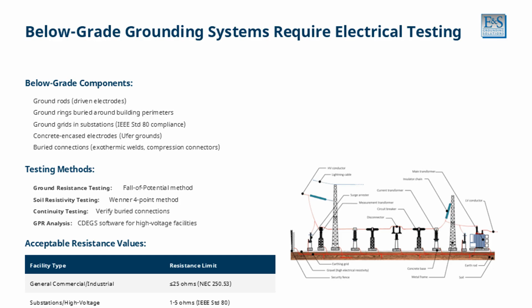Testing methods include ground resistance testing using the fall of potential method, soil resistivity testing using the Wenner 4-point method, continuity testing to verify buried connections, and ground potential rise analysis using CDEGS software for high-voltage facilities.